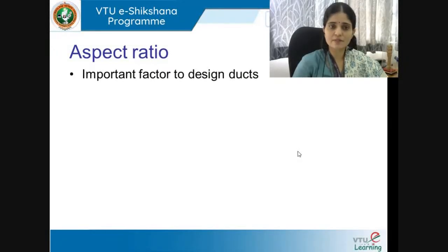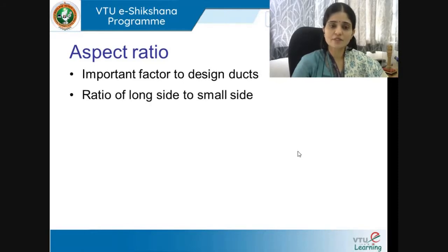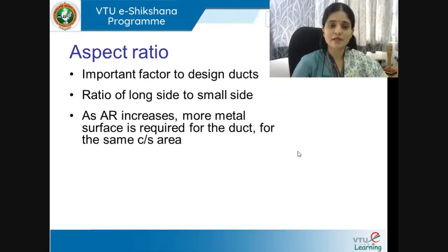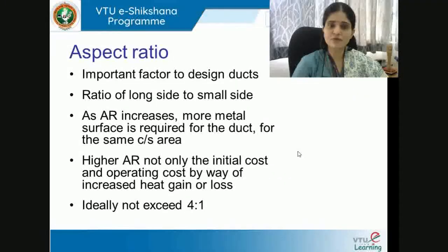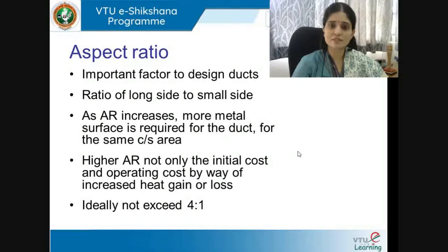Aspect ratio is an important factor in duct design — it is the ratio of the long side to the short side. As aspect ratio increases, more metal surface is required for the same cross-sectional area, increasing both initial and operating costs through increased heat gain or loss. Ideally the aspect ratio should not exceed 4:1, with 4 as the long side and 1 as the smaller side.